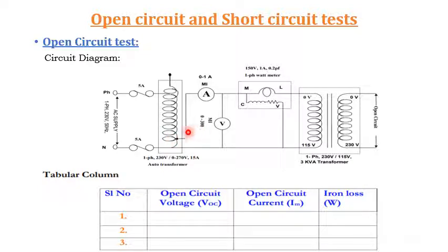Now the connections are made as per the circuit diagram. Here you can observe the transformer connection. This is a step down transformer, so this is the LV side of the transformer and this is the HV side of the transformer. In the open circuit test, the HV side of the transformer is kept open. Then the LV side of the transformer is energized by the supply voltage, and some meters are connected in between the supply and the LV side of the transformer. Those are the wattmeter, ammeter, and voltmeter in order to measure no load power, no load current, and supply voltage.